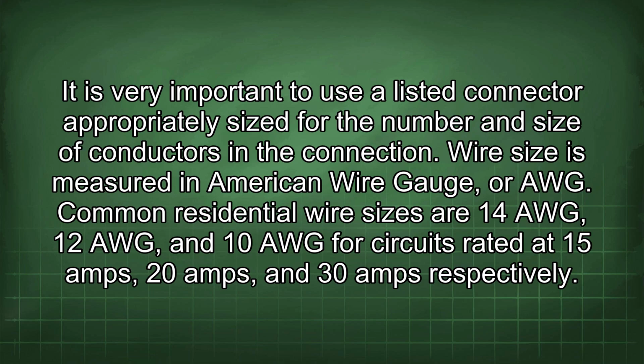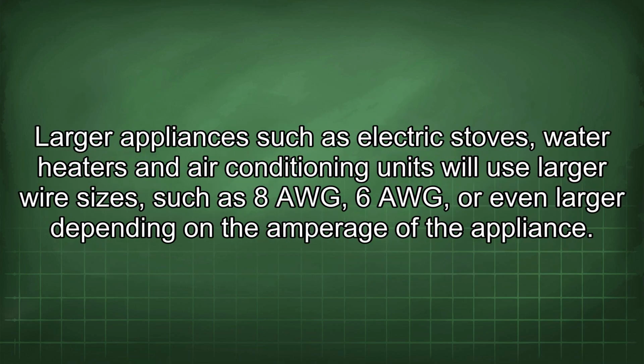It is very important to use a listed connector appropriately sized for the number and size of conductors in the connection. Wire size is measured in American Wire Gauge, or AWG. Common residential wire sizes are 14 AWG, 12 AWG, and 10 AWG for circuits rated at 15 amps, 20 amps, and 30 amps respectively. Larger appliances such as electric stoves, water heaters, and air conditioning units will use larger wire sizes such as 8 AWG, 6 AWG, or even larger depending on the amperage of the appliance.